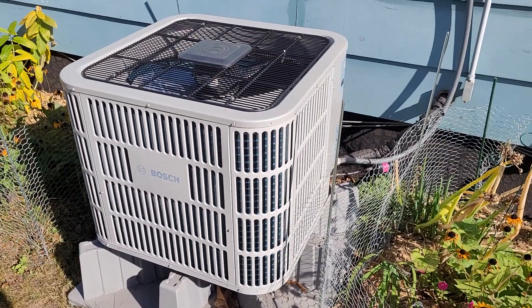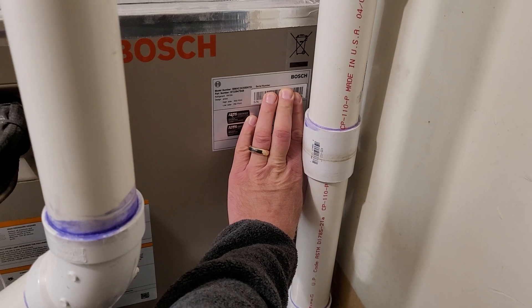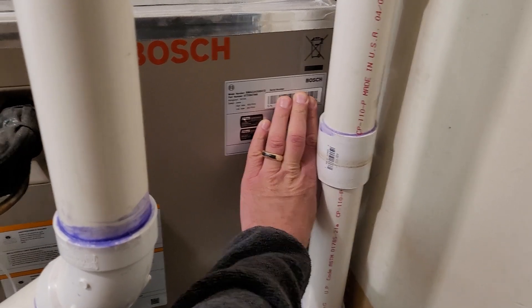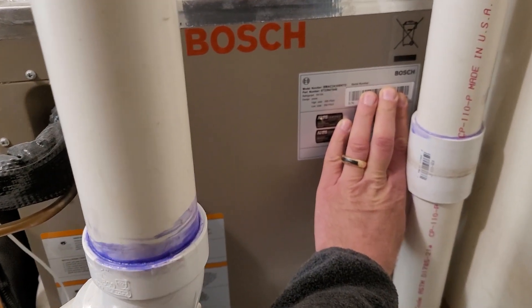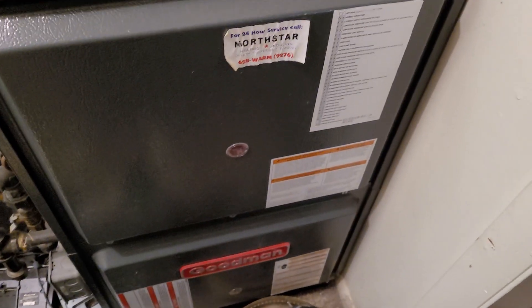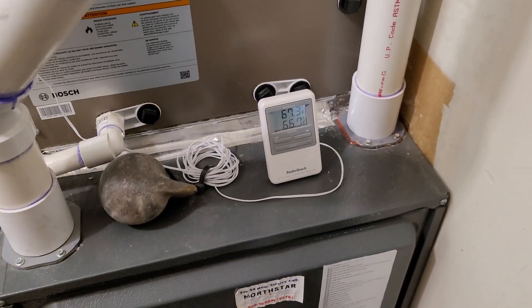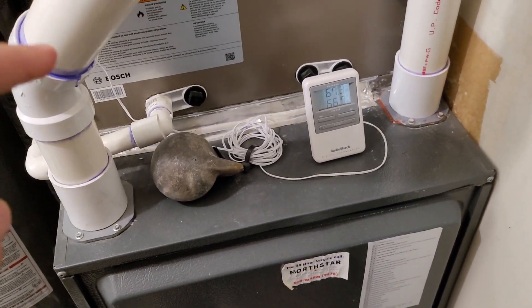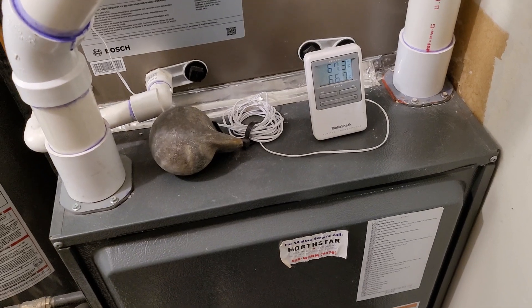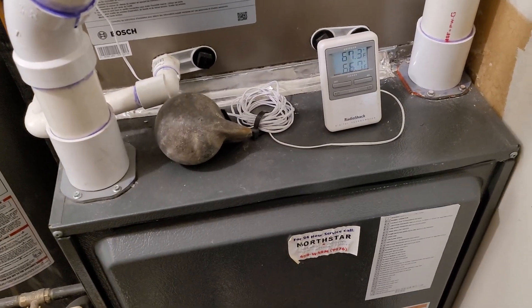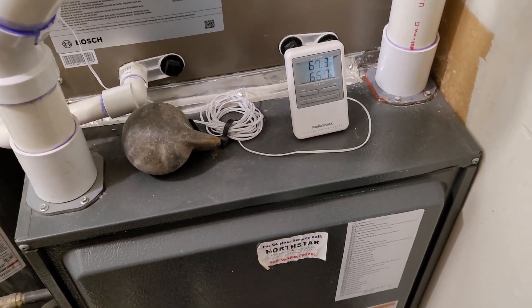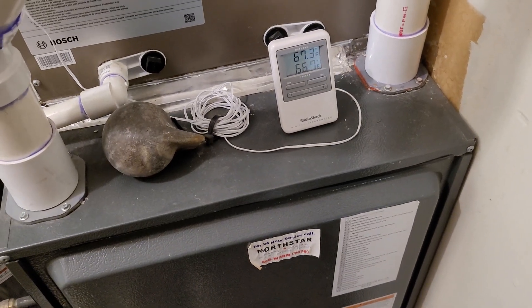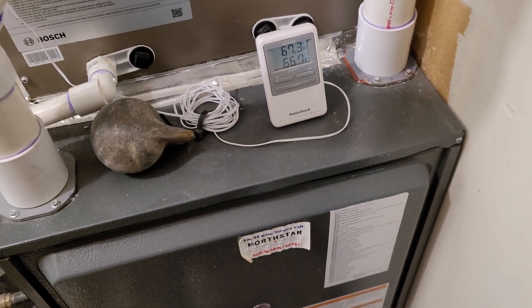So this is my air exchanger over here. It's got the coils inside it, and then I got a Goodman furnace down here. Now they recommend that you—I have a downflow furnace here, and they recommend that you put the air exchanger on the outside, on the outgoing air, and you really need to do that. You'll have condensation issues and water and it's not good. They should have put it the other way.